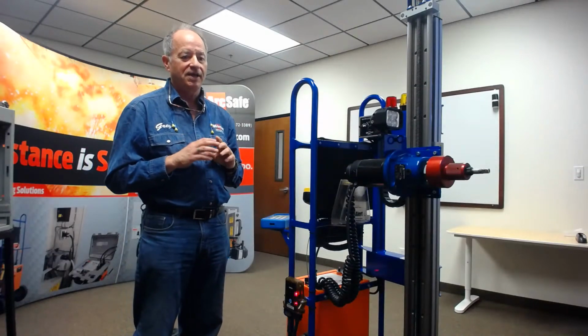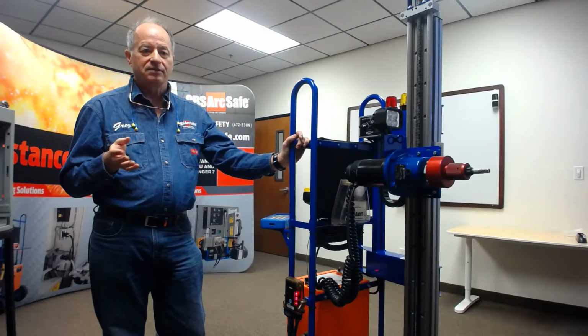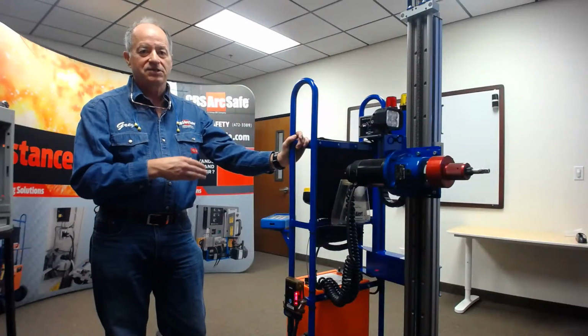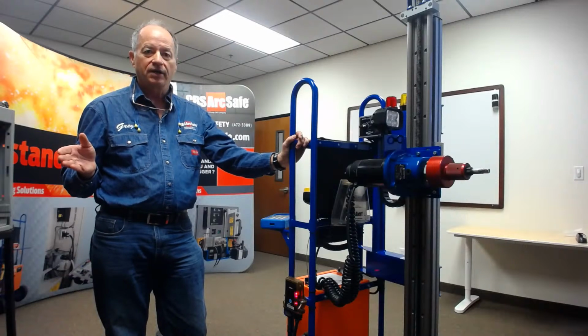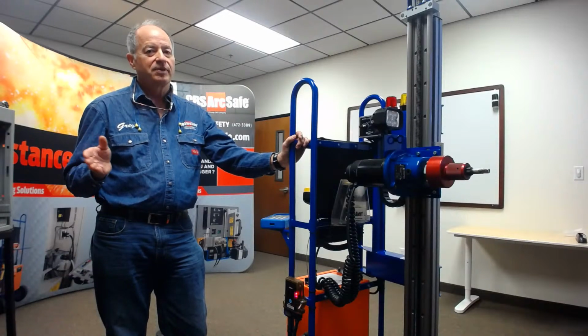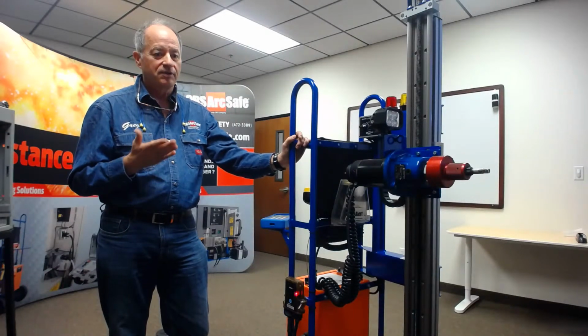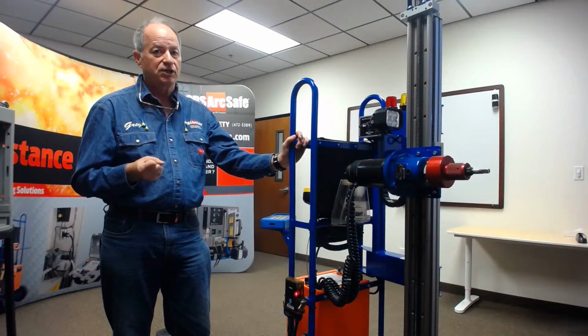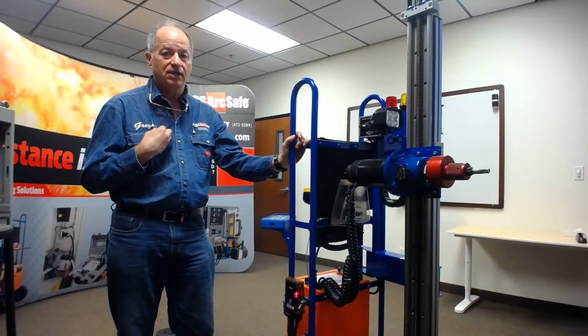And up until that day, the power plant manager, John, would have said, Bubba, get down on your hands and knees, rack the breakers. And he gets down to the last one, he says, I think that was harder than the rest, John. And the answer would have been, Bubba, you just racked 9 breakers. Your arm getting tired. But you've got an ability with the remote on the radio to read out the force that's actually being used.